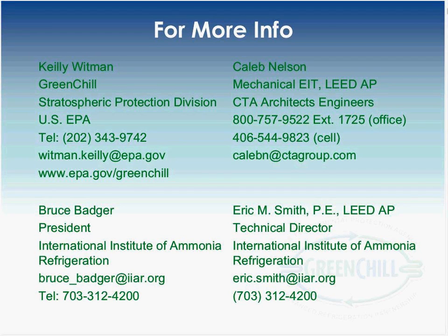The technology in industrial applications actually is there. I don't believe it has been considered for markets yet, but I think it's a good thing to look into. One drawback is the quality of the discharge heat - it's not really hot enough to do a lot of work. So what's needed is a separate subsystem to increase the quality of the heat, such that the temperature difference between the water and the discharge gas is greater. I'm not so sure it would be economically feasible in a supermarket situation - additional equipment would have to be bought, and that would have to be weighed against the benefit for water heating.